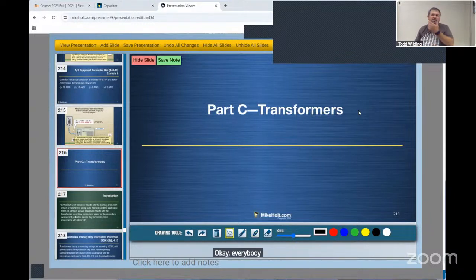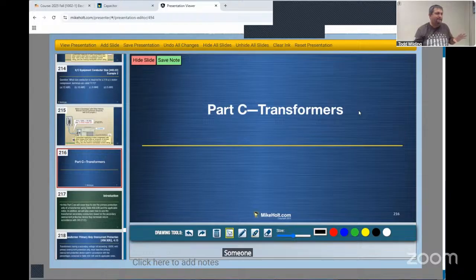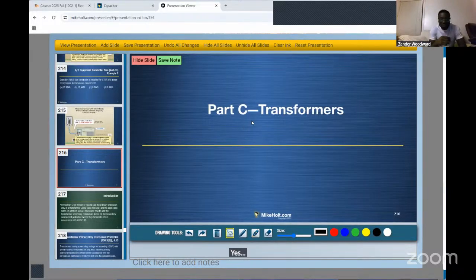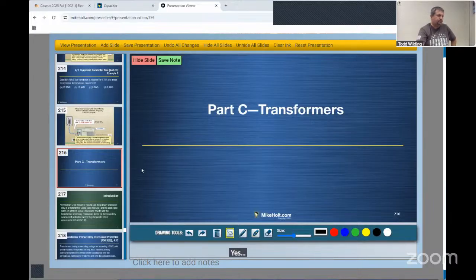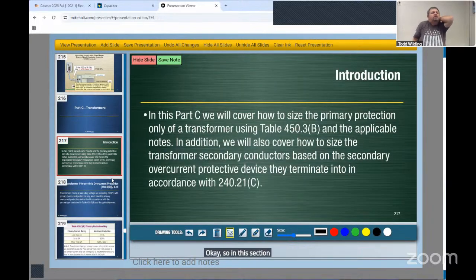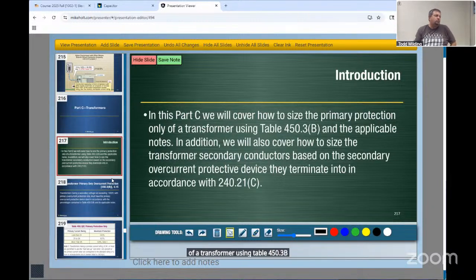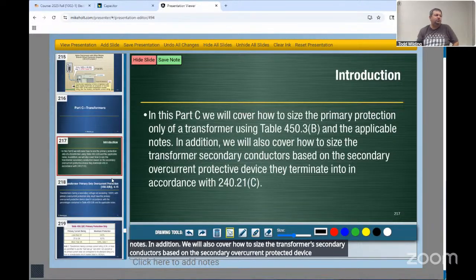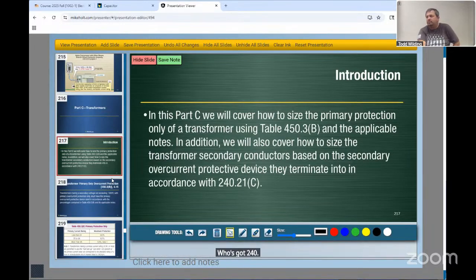Okay, everybody can see this slide presentation at home? Yes. Okay, so Part C of this is transformers. In this Part C, you'll cover how to size the primary protection only of a transformer using Table 450.3(B) and the applicable notes. In addition, we will also cover how to size the transformer secondary conductors based on the secondary overcurrent protective device they terminate into, in accordance with 240.21(C). Who's got 240.21(C) and wants to read it, please?